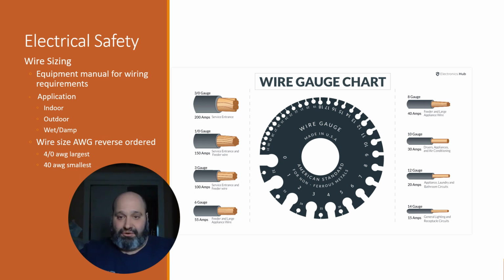So we had a no cool call on an apartment. Went with him, and the indoor blower would turn on, but it wasn't making cool. So we go down to the outdoor condenser, and I take off the mechanical compartment and find that there's a burned up wire. I mean, okay, no problem. So he just finds a random piece of wire that was obviously not the same gauge as the wire we were going to replace. So we're going to splice in a new wire. Nowadays, I would have hopefully taken that whole piece of wire from one end to the other, with new contactors and new terminal ends, and replaced the whole wire. But back then, my fix was replace that burnt piece of wire, which, I mean, it's not terrible. But it wasn't the right gauge wire, and he insisted that it was fine.